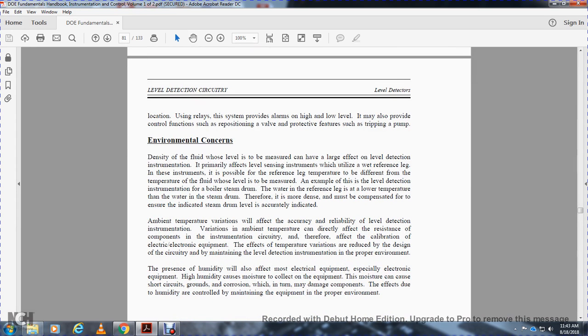Environmental concern. The density of the fluid whose level is measured can have a large effect on the level detection instrument. The primary effect on the level instrument using a wet reference leg is probably the reference leg length and the temperature of the fluid whose level is to be measured. For example, with the level detection instrument on a boiler steam drum, the water in the reference leg is at a lower temperature than the water in the steam drum, and therefore more dense, and must be compensated for, or the instrument's indicated steam drum level will be in error.